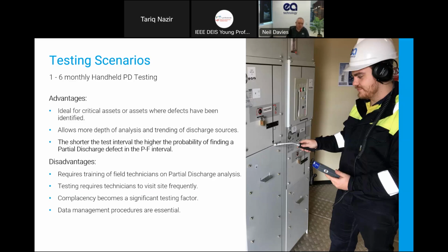One thing to be aware of, if you are testing regularly and you're finding nothing, is that complacency becomes a significant testing issue. So if I'm going to the same substation every month and I'm testing and finding nothing every month, am I still really doing the best job after month 6, 7, 8, 9, 10?